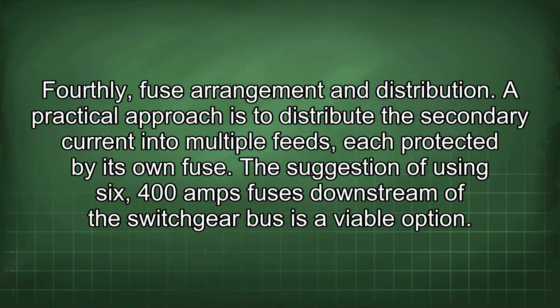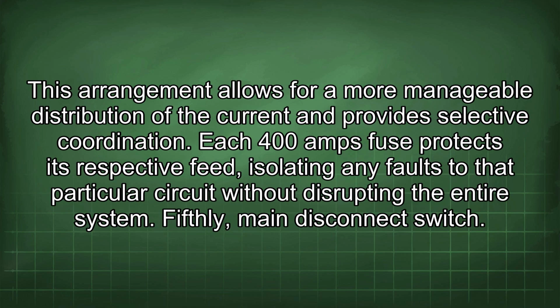A practical approach is to distribute the secondary current into multiple feeds, each protected by its own fuse. The suggestion of using 6 400 amps fuses downstream of the switchgear bus is a viable option. This arrangement allows for a more manageable distribution of the current and provides selective coordination. Each 400 amps fuse protects its respective feed, isolating any faults to that particular circuit without disrupting the entire system.